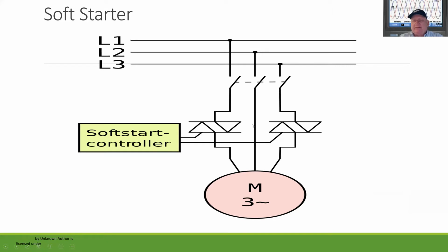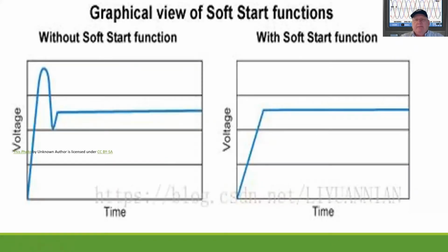So you have 3 of these. There actually would be one more in there. You'd have 3 of these in the circuit feeding the 3-phase motor in a soft start controller. The main focus of this is to eliminate the high inrush current. So when you put 460 volts initially right to the motor winding, like a starter did, the motor ends up, because it's not up to speed, drawing a very high current spike. So you turn on the 460 volts, the motor is not turning, and you get inrush currents of anywhere from 3 to 6 times the actual rating if you don't control that voltage when it comes in.